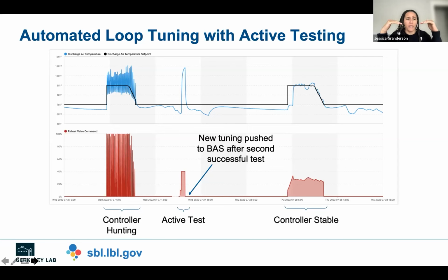So on the top plot, you will see discharge air temperature in blue and the temperature set point in black. On the bottom, you see the command status of the reheat valve. So the first thing you see in the red is that valve going open, shut, open, shut, open, shut, just really oscillating. And you also see in blue that we're bouncing all around that set point.